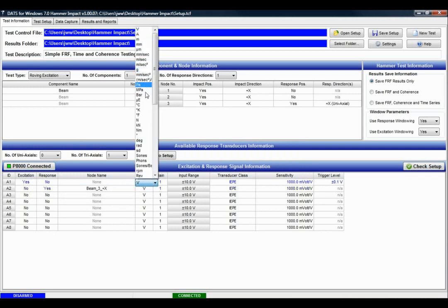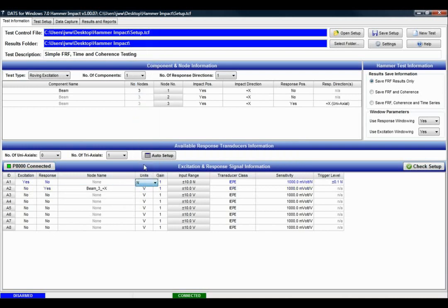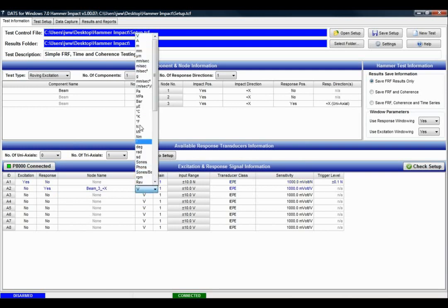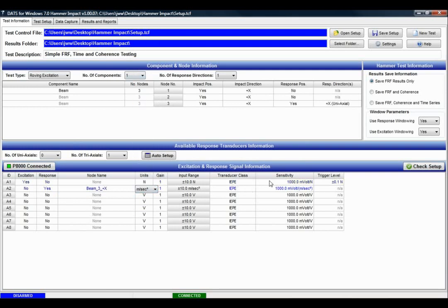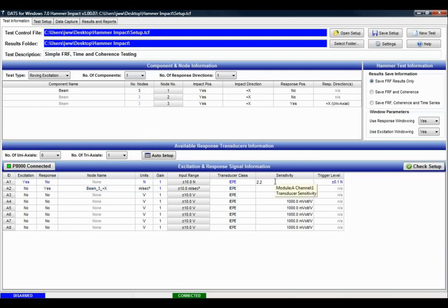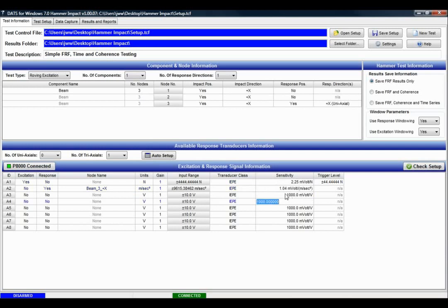I need to set some of the parameters about the signals. I need to set the sensitivity for the hammer which is 2.25, and the sensitivity for the accelerometer which is 1.04. In this particular case I'm going to...